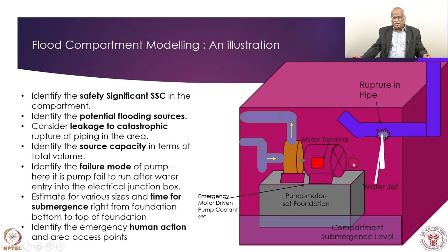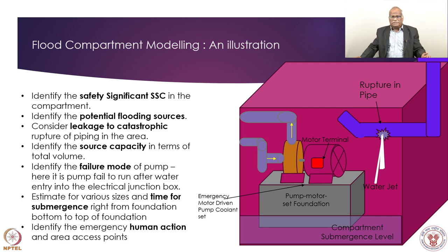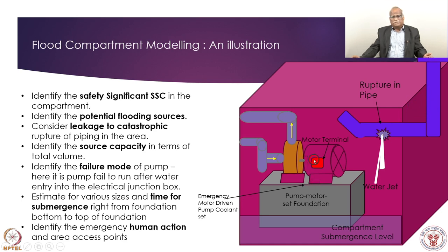These pipes are normally sturdy and do not fail, but PRA is about postulation. If the pipe fails, water should not reach the junction box or bearing shaft level — this is how we model the threat and how to handle this scenario. Redundant pumps should be provided in a different area or at a different elevation. There should be a wall that can be closed immediately — perhaps motor-operated. These arrangements exist in the plant, but combinations of failures can lead to such events.